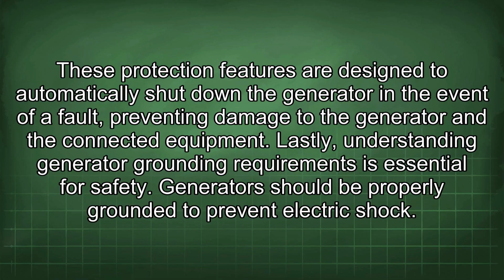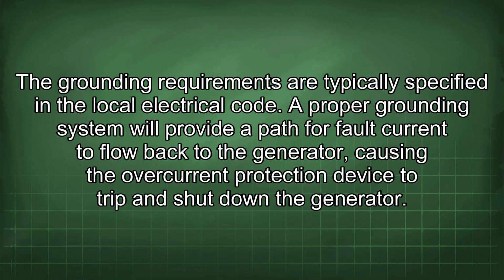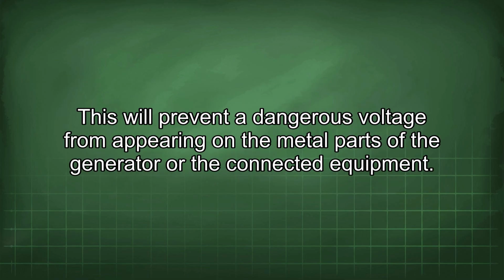Lastly, understanding generator grounding requirements is essential for safety. Generators should be properly grounded to prevent electric shock. The grounding requirements are typically specified in the local electrical code. A proper grounding system will provide a path for fault current to flow back to the generator, causing the overcurrent protection device to trip and shut down the generator. This will prevent a dangerous voltage from appearing on the metal parts of the generator or the connected equipment.